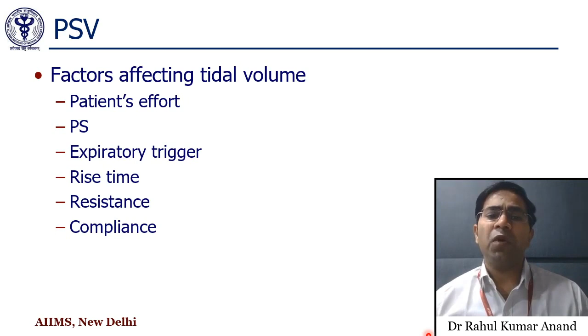Then there is the expiratory trigger. Expiratory trigger tells us about the inspiratory time. If we keep the expiratory trigger towards the lower side, maybe 10, that means once the peak inspiratory flow rate reaches 10% of its original, then expiration will start. That means more time will be available for inspiration, and if more time is available, more tidal volume will be there.